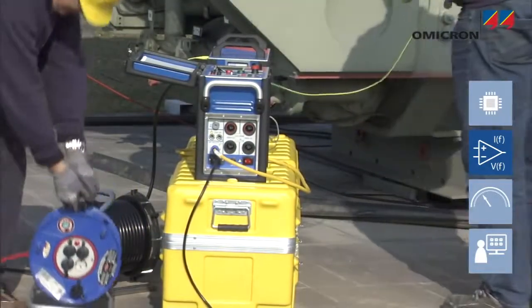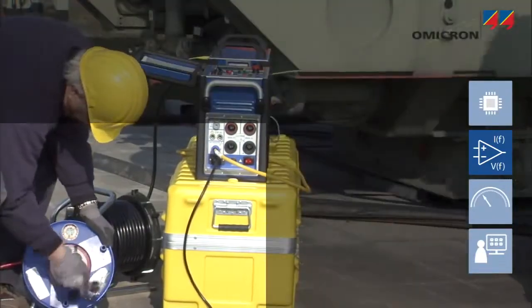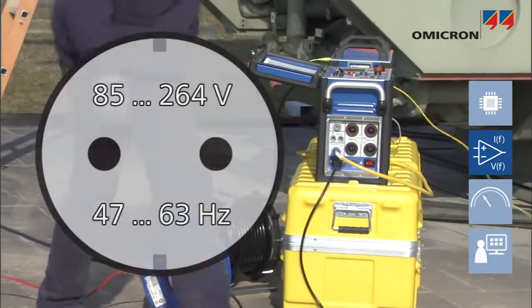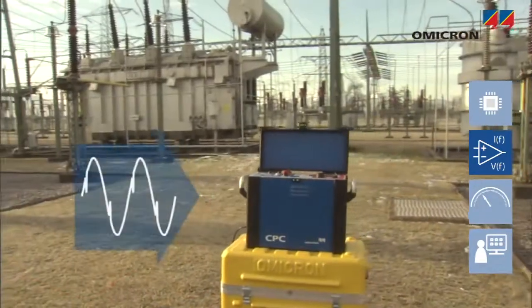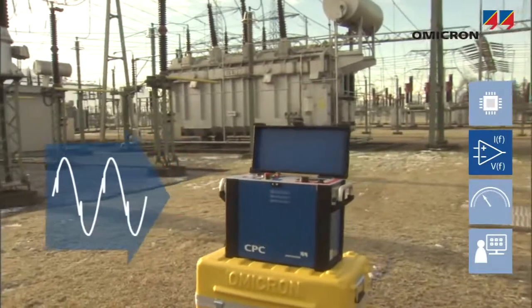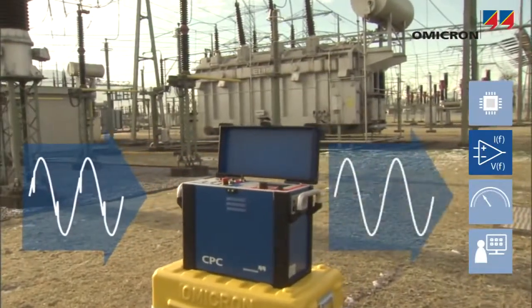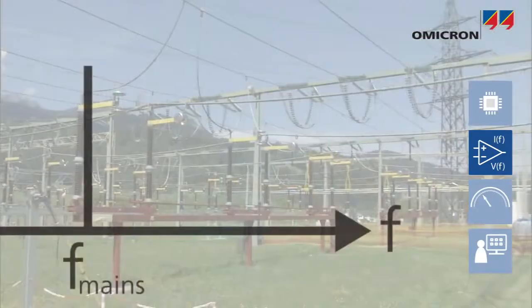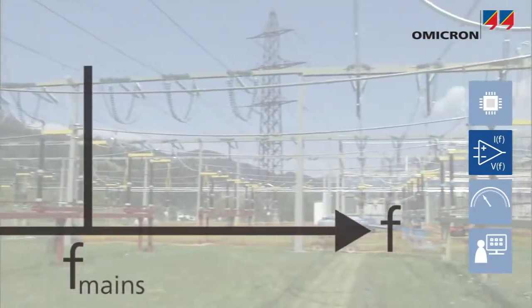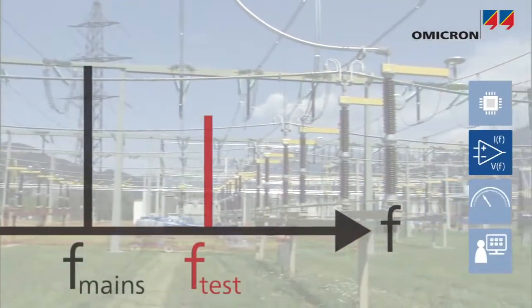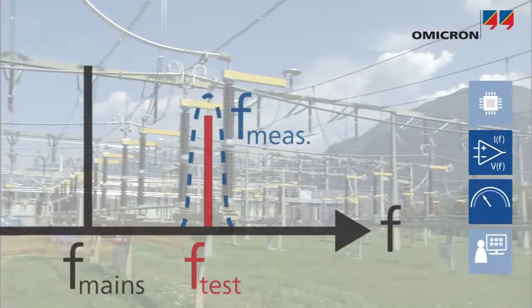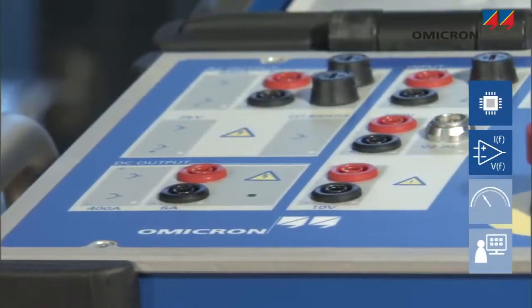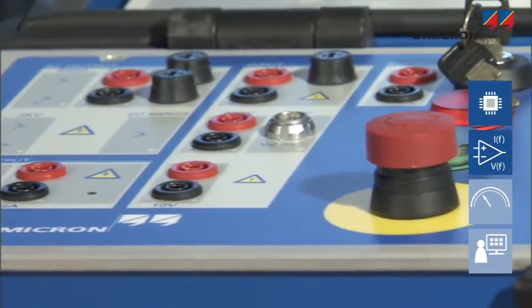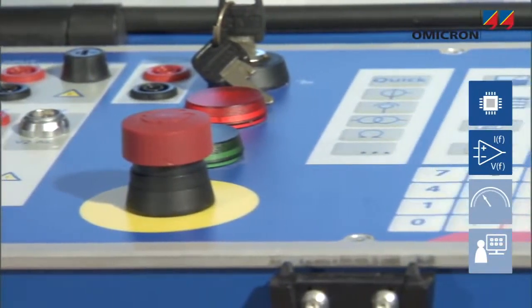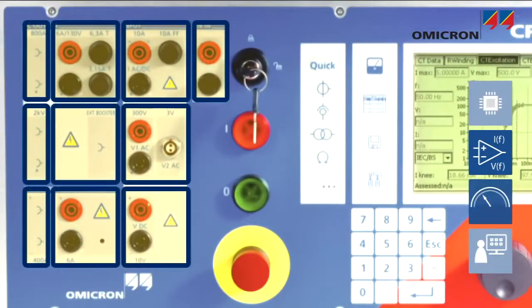Generating reactive power internally, the CPC can provide all its output values when supplied by a standard wall socket. The supply voltage has no influence on amplitude, frequency, or waveform of the output signals due to digital signal generation. Mains frequency interference can be avoided by using variable frequency test signals and frequency selective measurement. All outputs are protected against short circuits, open circuits, overloads, and overtemperature. Galvanic isolation of all outputs and inputs prevents unintended ground loops.